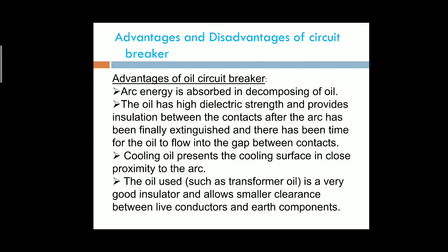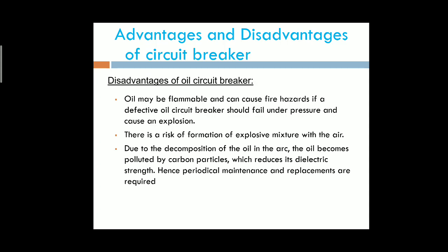The oil is a very good insulator and allows smaller clearance between the live conductors and the earth. Next, it is a low cost circuit breaker. The oil has a high dielectric strength and provides insulation between the contacts after the arc has finally been extinguished, and there is time for the oil to flow into the gap between the contacts.